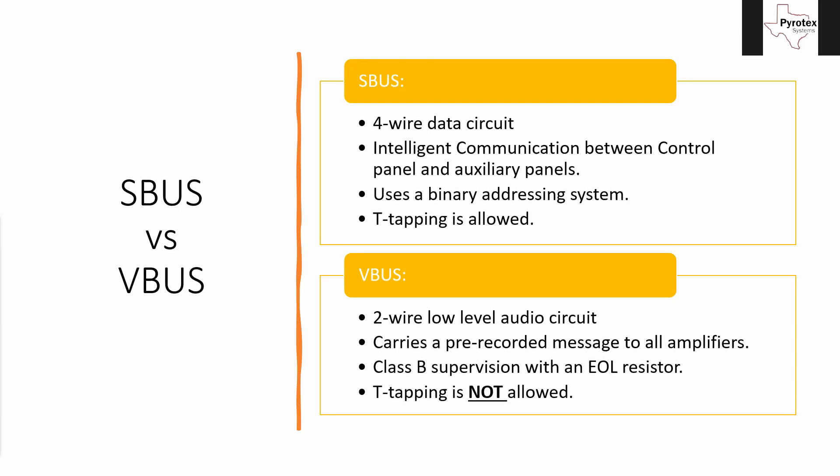SBUS and VBUS, even though they sound very similar except for that first letter, are entirely different things. SBUS is a four-wire data circuit. It does digital communication — intelligent control between the control panel and all of its auxiliary panels, whether they're annunciators, remote microphones, power supply panels, or amplifiers. It controls all the inputs, outputs, and displays. All the intelligent things that happen in a Silent Knight or Farenhyt panel are communicated over the SBUS, including extra SLC loop cards for loop two, loop three, and so on.